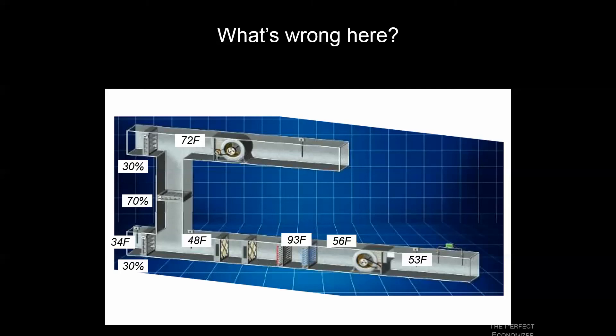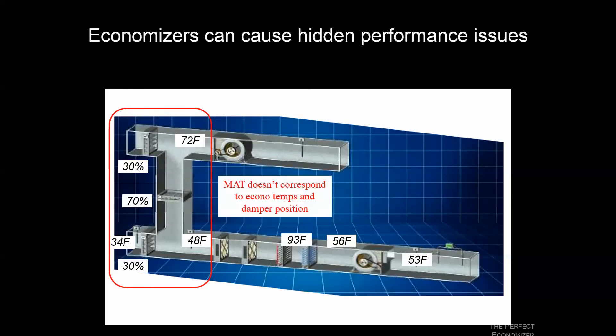Back at the BAS workstation — now understanding that the economizer operates on a continuum of modes — this graphic screen is a snapshot along the economizer profile. We can see that with 70% return air and only 30% outside air at these conditions, the mixed air temperature should be much closer to the return air condition. This exposes competing control loops: the system is now using preheat and then cooling that air back down, showing how economizer issues can have downstream trickle effects throughout the system.